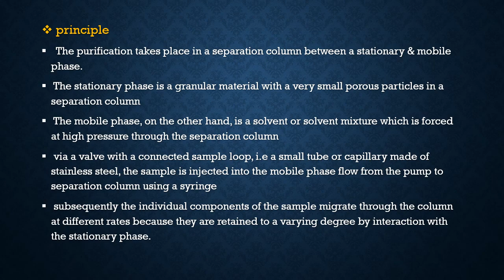So via a valve with a connected sample loop, that is a small tube or a capillary made up of stainless steel, the sample is injected into the mobile phase flow from the pump and separation column using a syringe. Subsequently, the individual components of the sample migrate through the column at different rates because they are retained to varying degrees by interaction with the stationary phase because of their nature. Because they are either hydrophilic or hydrophobic, according to that they are separated.